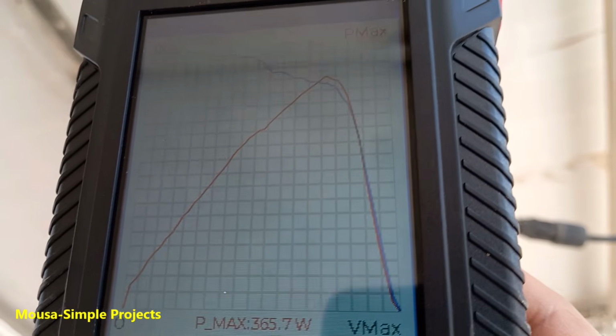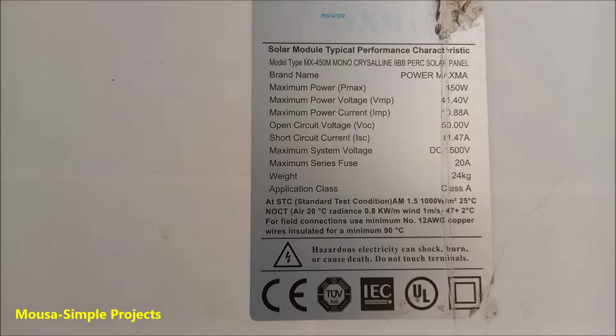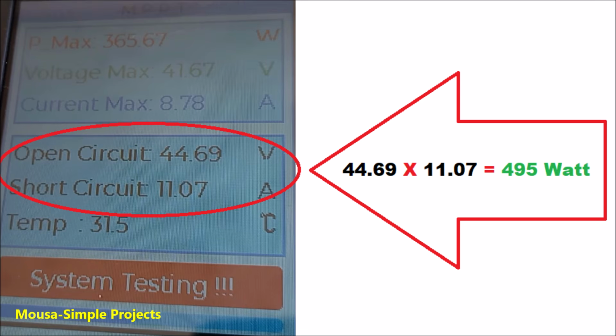Even the IV curve is different than the other panels. The backside of this solar panel is not in good condition. You see, this is why you need a solar tester, because if you use a multimeter, it's going to show you that this solar panel is good, since the short circuit current and open circuit voltage are completely normal.